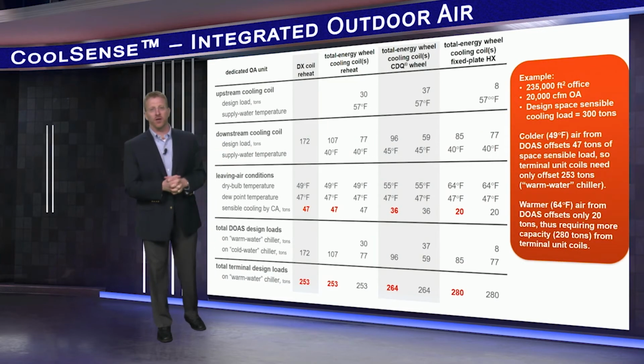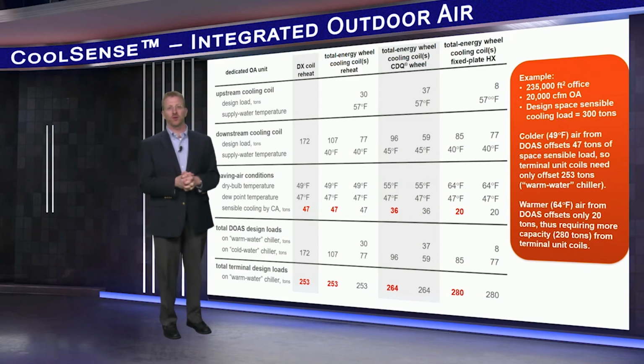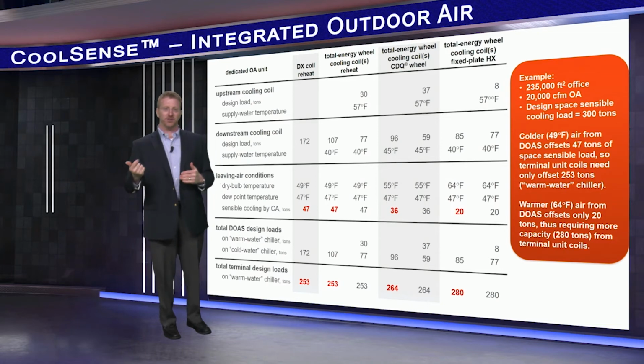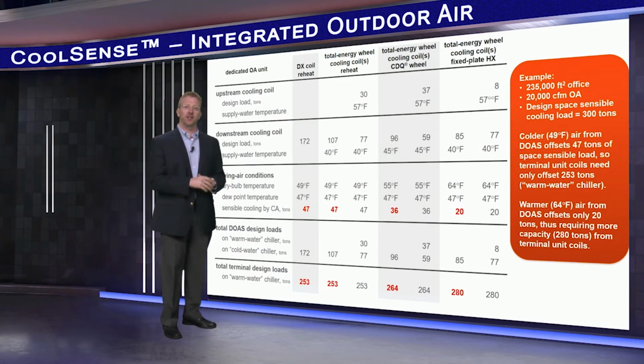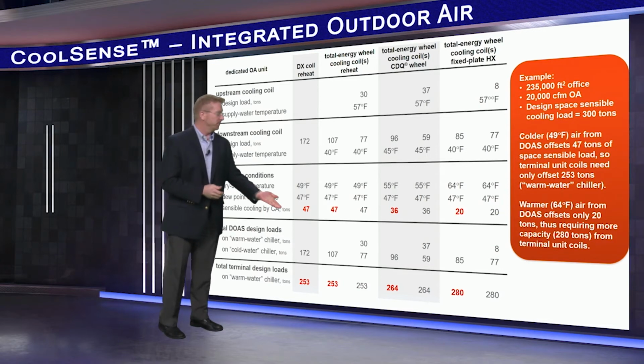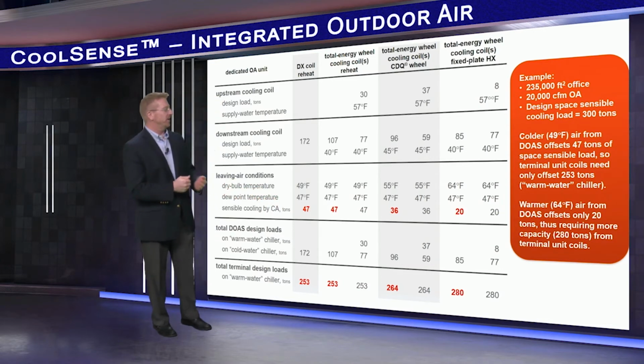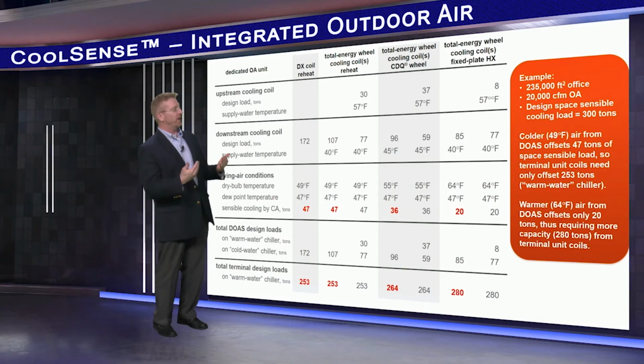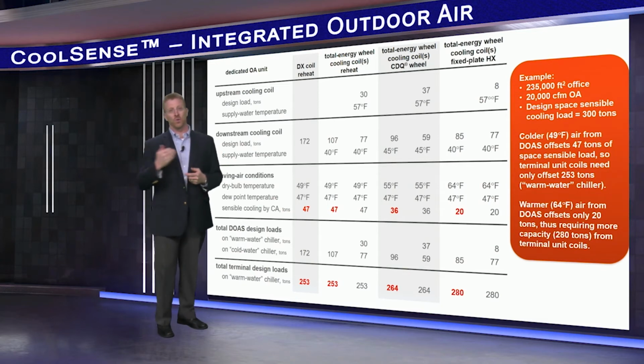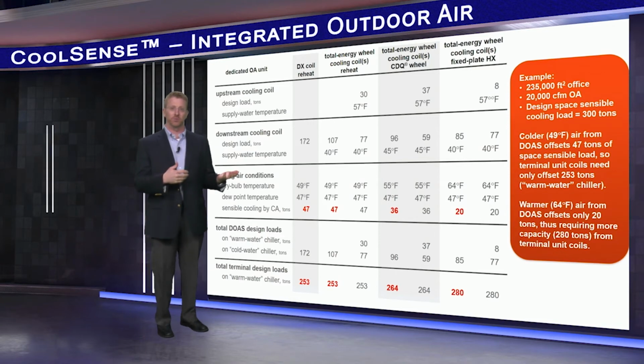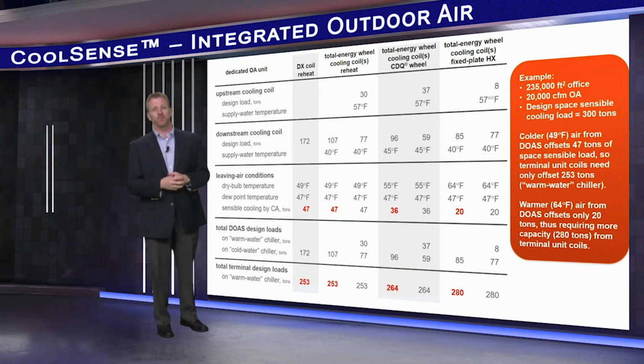So let's look at some takeaways. This table transfers all those values from the 6 different DOAS configurations and adds in the standard DX unit for comparison. Focusing in on the red values, this comparison shows a designer that can leverage different DOAS configurations to advantage their design, shifting loads to the warm water loop or the cold water loop, depending on the application and desired chilled water plant configurations. More on that in a moment.